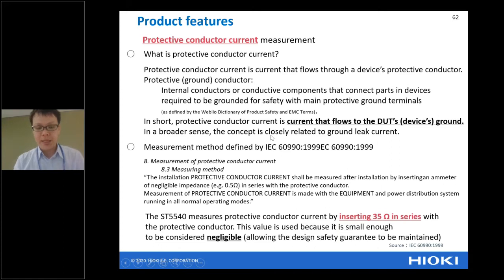From the standard, sometimes you have to measure protective conductor current. For the ST5540, as I told you, for leakage current measurement you can insert the human electrical circuit up to the standard. But if you want to measure protective conductor current, the standard says to insert a very, very small resistance. So the ST5540 can insert 35 ohm in series with the protective conductor. That's why our ST5540 is available for this measurement from the standard also.